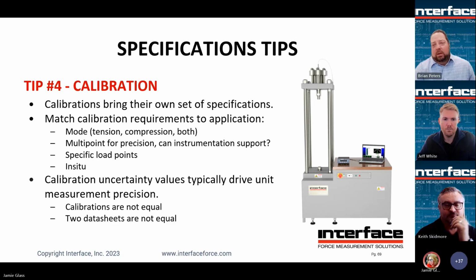Calibration. We could do a whole other webinar on calibration, but for best performance and best match, you want to try to ensure your calibration is as close as possible to what your actual test is going to be. So do you have tension or compression data? Do you need both? Do you only need one? Like we talked about several times, can you run a multi-point cal instead of just a single full-scale value? That's true for the sensor too. If you're looking at the sensor specs, what kind of cal does it come with? Do you have a multi-point? Do you have a single point? And the last part is, what is the uncertainty of the calibration? That's usually a separate question you need to ask. You can be looking at two data sheets side by side, but if one has 0.04% or 0.02%, if it's a dead weight type cal versus an unknown or unaccredited cal, it makes your measurement a little bit risky.